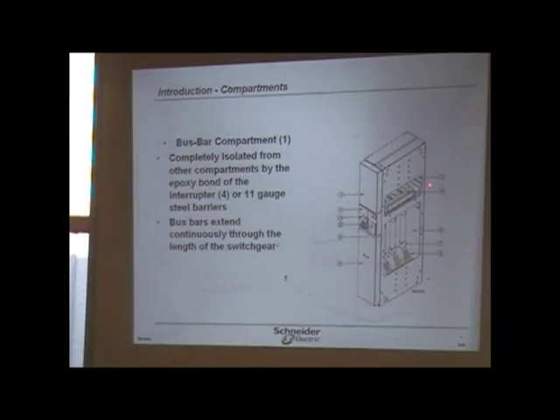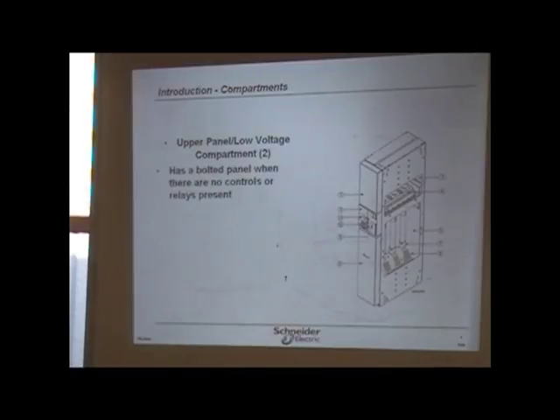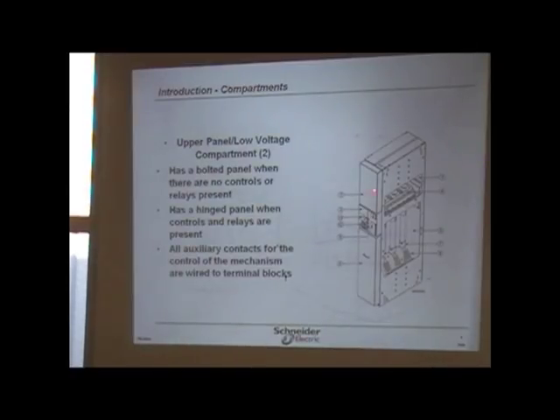The bus bar compartment, it says number 1. Of course, there you go. The bus compartment, the bus will be coming through there. 11 gauge steel barriers. Bus bars extend continuously through the length of the switchgear, which would be right up at the top over here. Go straight across. Number 2 was that low voltage compartment that we talked about. If you open it up, you would see the low voltage stuff, and we'll see it out there as well.